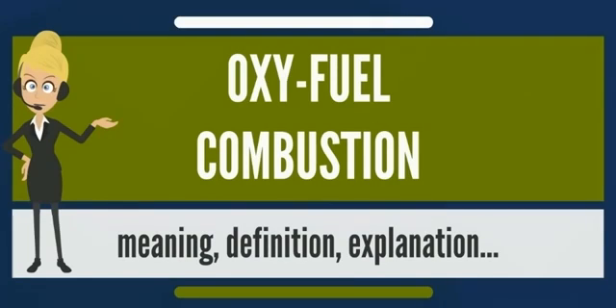Economically speaking, this method costs more than a traditional air-fired plant. The main problem has been separating oxygen from the air. This process needs lots of energy — nearly 15% of production by a coal-fired power station can be consumed for this process. However, a new technology called chemical looping combustion, not yet practical, can be used to reduce this cost.